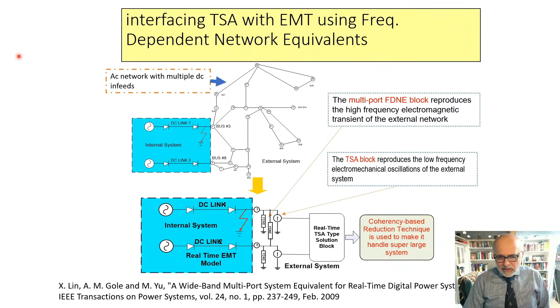In this particular case, we had modeled this on a real-time simulator, but it doesn't matter whether it's a real-time or offline simulator, the same technique can be used. You have transient stability analysis on this side, and you've got the full EMT simulation on this side. You've got the interface here, which really is just a current source that transfers the TSA information to the DC link. But in addition, you also have these frequency-dependent network equivalents, which you put on that bus bar, and they represent the high-frequency behavior of the AC network so you get accurate simulations even at high frequencies.